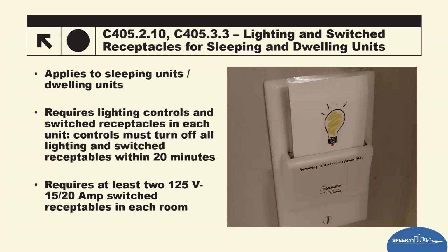And then lighting and switched receptacles for sleeping and dwelling units, such as apartments. Basically, it ensures that within these units in commercial buildings, the lighting and receptacles that are on the switch are under a control that reduces plug and lighting loads when unoccupied. It mandates foundationally the electrical switching infrastructure. So it's about managing plug load and lighting in spaces that are most of the time overlooked in commercial compliance.